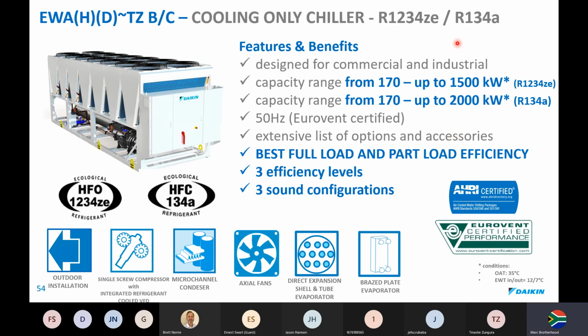Now we're getting onto the bigger chillers, the bigger capacity ranges, also an inverter. We offer this in R1234ZE refrigerant as well as R134A. Important to note, though, that depending if this is sort of a green building design, HFO 1234ZE, when it comes to a global warming potential, it's lower than carbon. Carbon is 1. This is about 0.7 something. It's much lower than carbon.